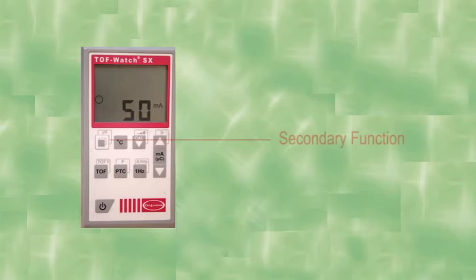The button here is the secondary button. If we press this and subsequently press the TOF button, the activation of the TOF in series, which is in light gray behind, will be activated. By pressing the secondary button and the TOF, we can activate the series which can be programmed. The duration of the TOF may be set to repeat once in half an hour or 45 minutes as may be required in the intensive care units. A press of this will initiate post-tetanic count. As you know, post-tetanic count can be initiated only when the TOF reading is 0. In order to provide very deep blocks, we need to provide a block where the post-tetanic counts are also 0.